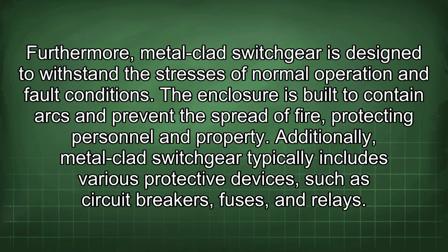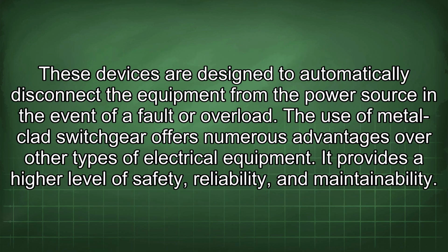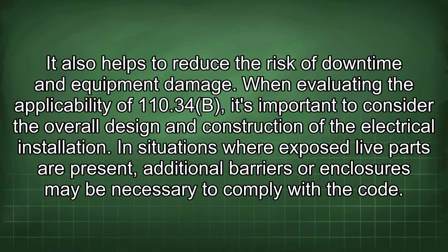Furthermore, metal-clad switchgear is designed to withstand the stresses of normal operation and fault conditions. The enclosure is built to contain arcs and prevent the spread of fire, protecting personnel and property. Additionally, metal-clad switchgear typically includes various protective devices, such as circuit breakers, fuses, and relays. These devices are designed to automatically disconnect the equipment from the power source in the event of a fault or overload. The use of metal-clad switchgear offers numerous advantages over other types of electrical equipment. It provides a higher level of safety, reliability, and maintainability. It also helps to reduce the risk of downtime and equipment damage.